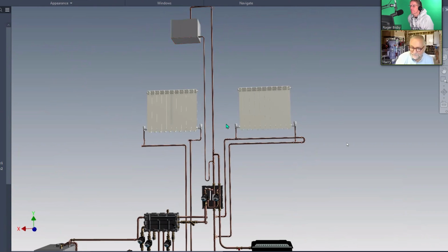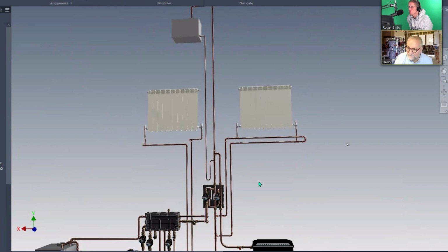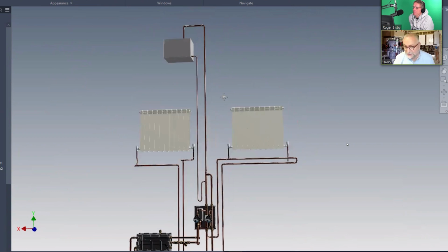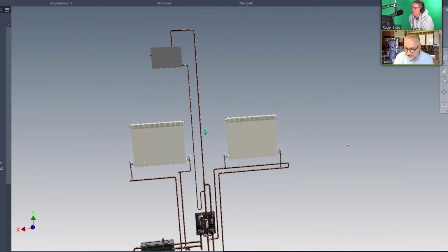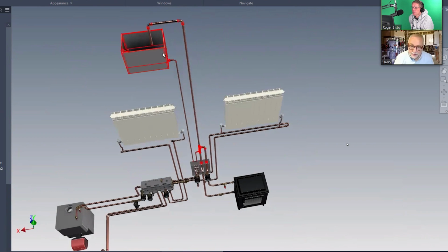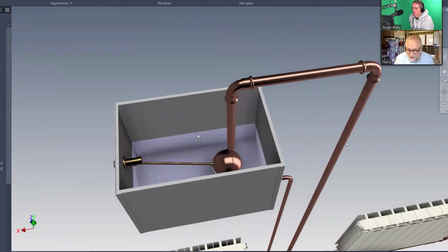So every time I've taken the lid off a feed and expansion tank and seen droplets of water on the underside of the lid, that is because it's trying to evaporate out of that tank into the loft. Yeah. So when you do this, you might remember this. It's a little trick. If you want to see if the heating system is done properly, you get a glass of water, you go to the attic, and you scoop out some of that water with your glass, stick the glass of water onto the expansion pipe, get someone to turn the system on and off. If that water moves a millimeter, something is wrong in your neutral point.